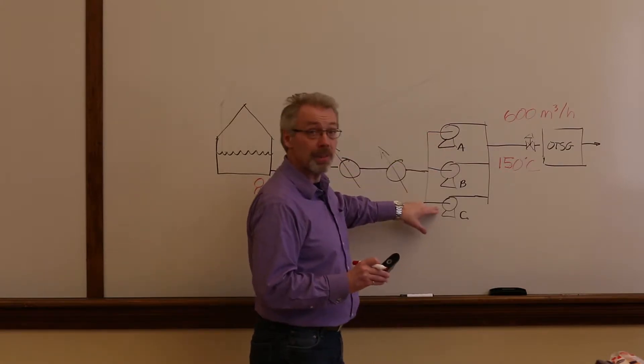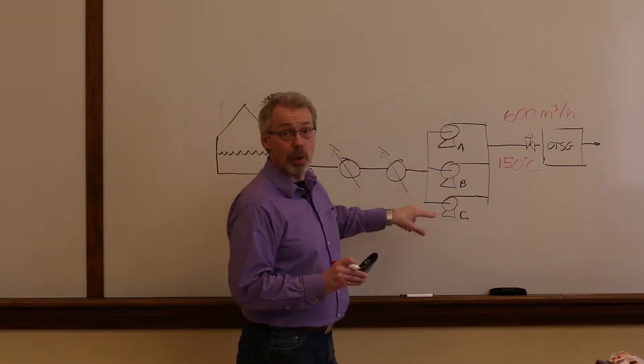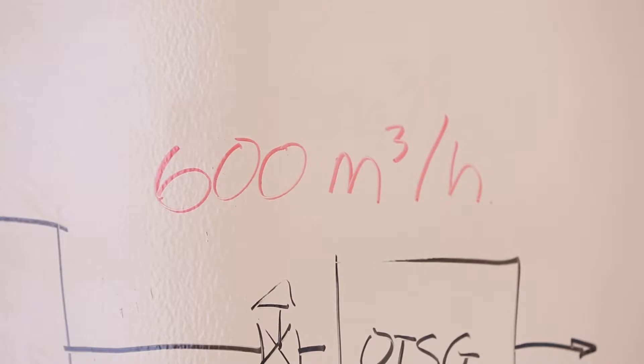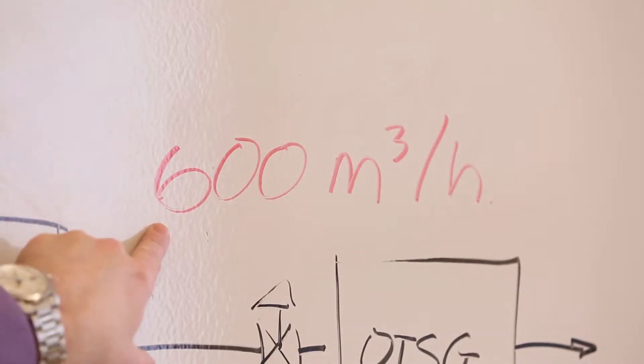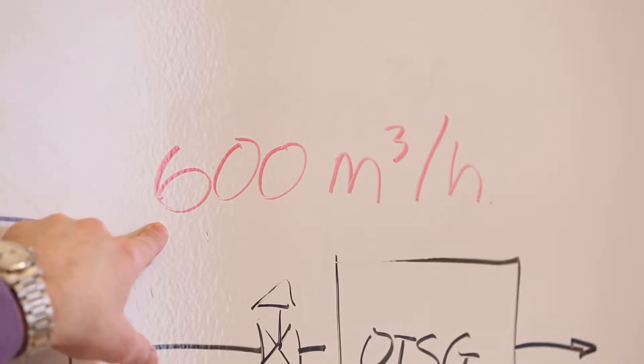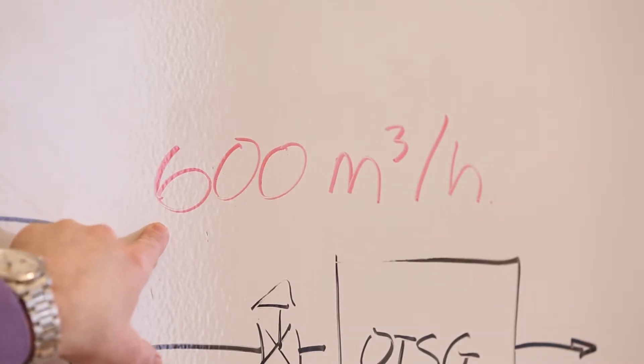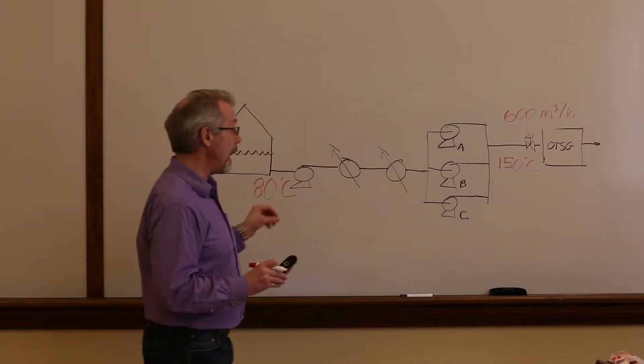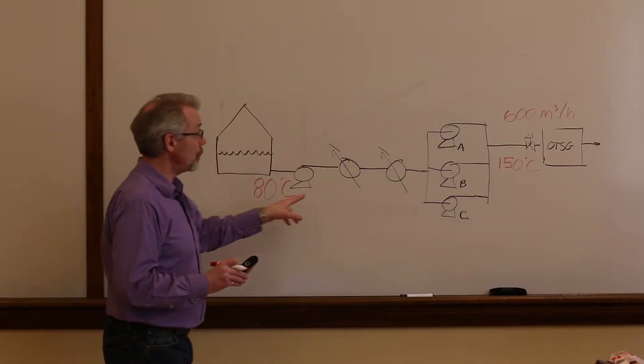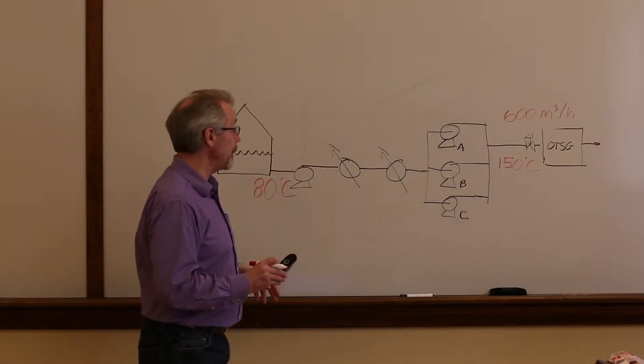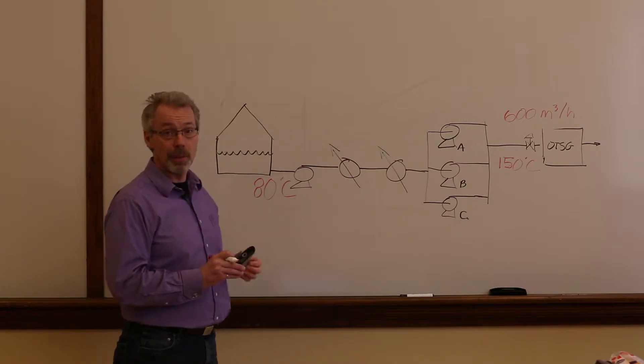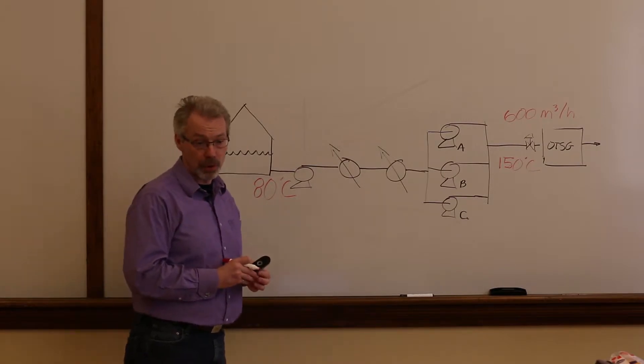The third pump, C, is offline. In this example, the total flow rate of water taken by the OTSG is 600 cubic metres an hour, and that produces a temperature rise of 70 degrees across the heat recovery section.